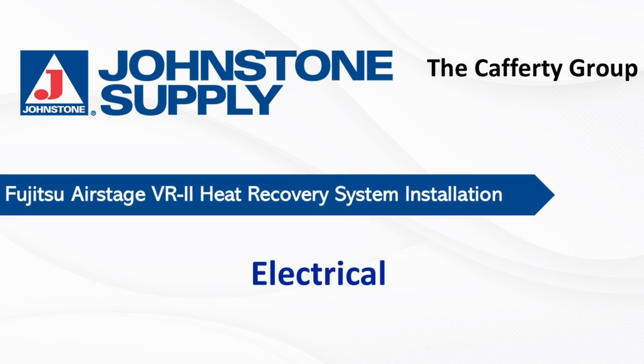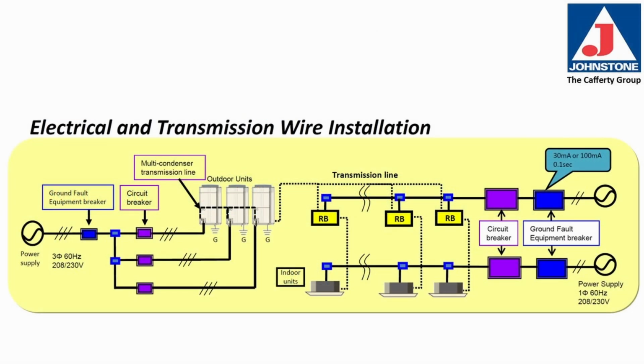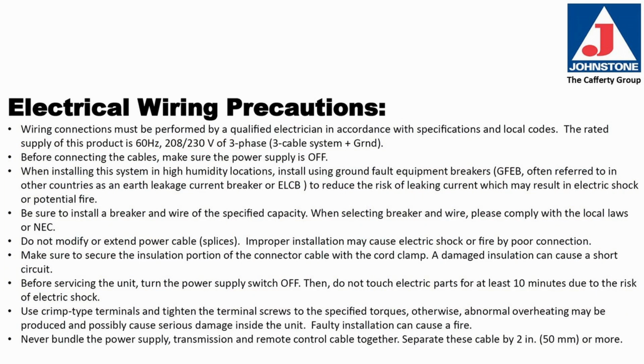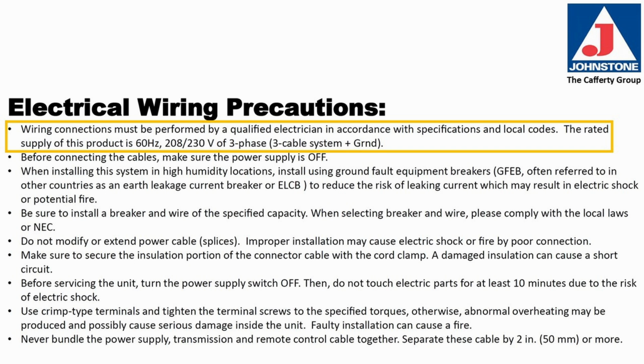System Electrical Installation. In this section, we will discuss electrical wiring and transmission wire installation. Electrical wiring precautions. Wiring connections must be performed by a qualified electrician in accordance with the specifications and local codes. The rated power supply for this product is 208-230, 60 Hz, 3-phase.